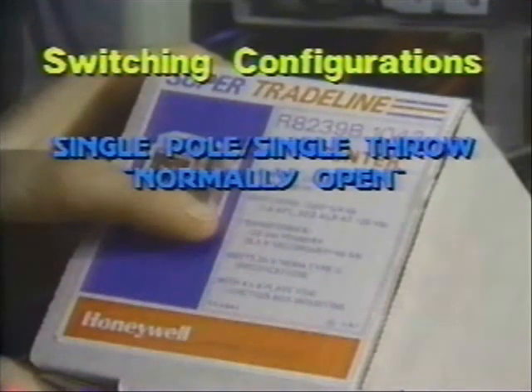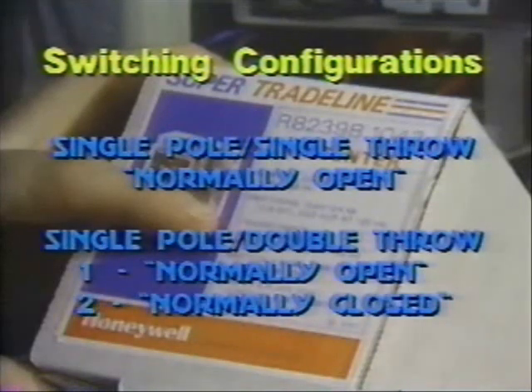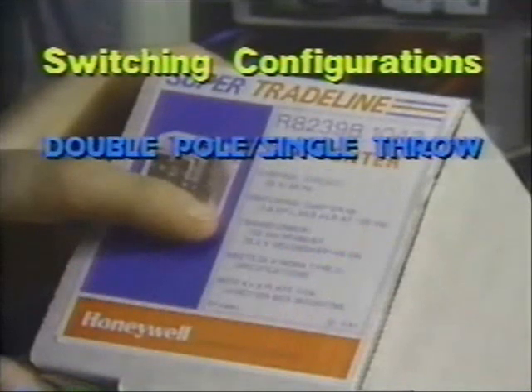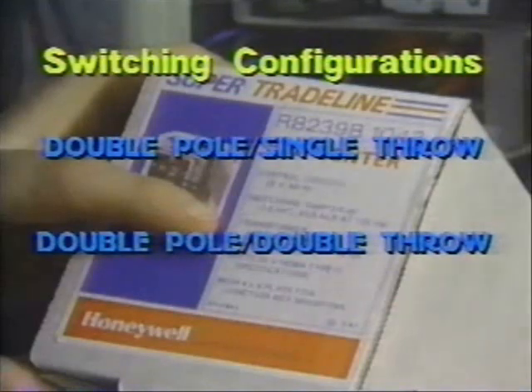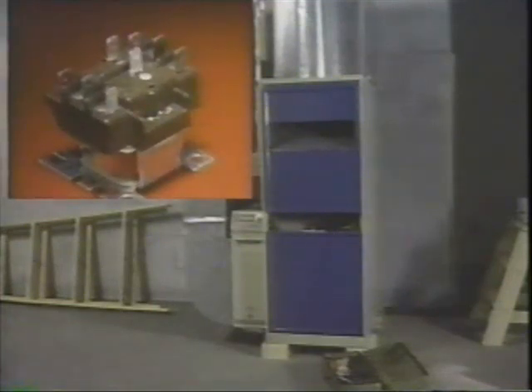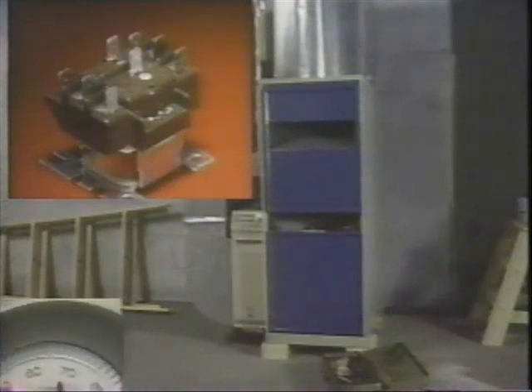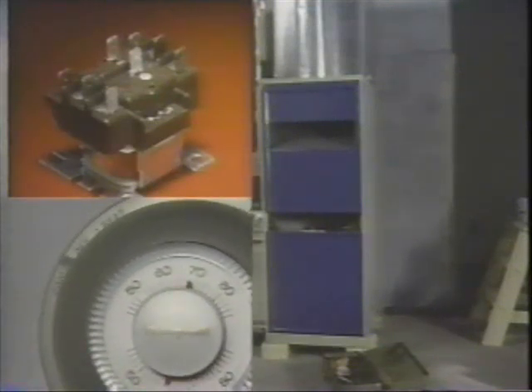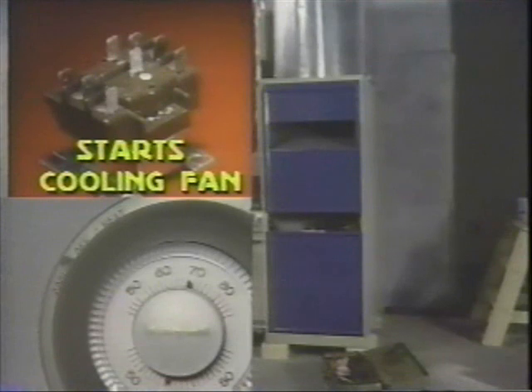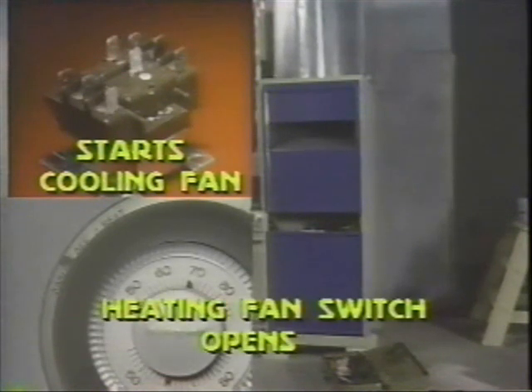Basic configurations include single-pole single-throw with normally open contacts, single-pole double-throw with one set of contacts normally open and the other normally closed, double-pole single-throw, and double-pole double-throw. In combination heating and cooling systems, single-pole single-throw switching is used when a relay's only job is to turn the fan on and off. When the thermostat calls for cooling, the relay pulls in to start the system fan. The switch that controls the fan in the heating mode is wired in parallel with the normally open relay contacts.